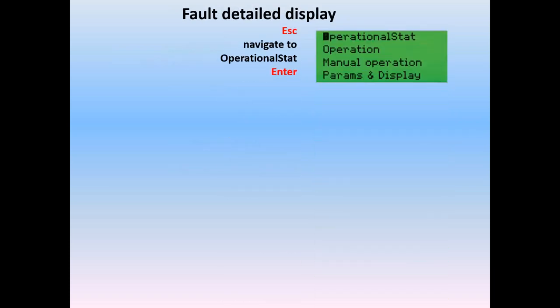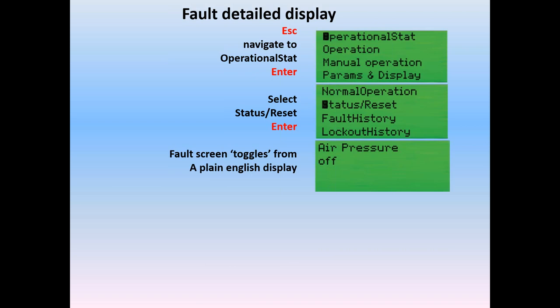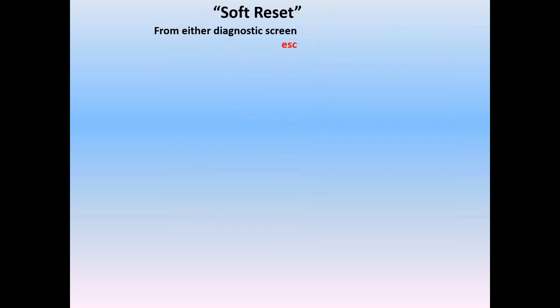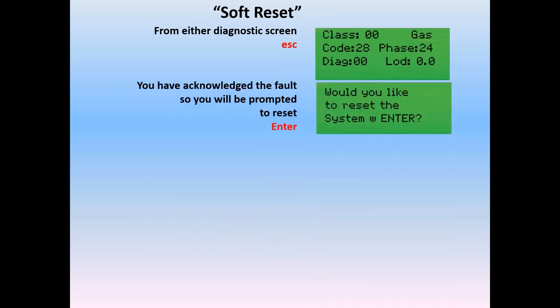From that screen, from operational stat, we escape, go back to operational stat, enter operational stat — just like the screen told us. In this case, we go to status reset versus normal operation and press enter on status reset. Now the screen toggles between the plain English 'air pressure off' and a much more detailed diagnostic display, giving us loads of information on the exact error at the current time. We can then perform a soft reset from either of the two diagnostic screens. We can simply escape the diagnostic screen. Since we have seen the fault in detail, we have acknowledged it and will be prompted if we'd like to reset the fault with enter. At this point, if you hit enter, reset is displayed on the screen and the fault is cleared.